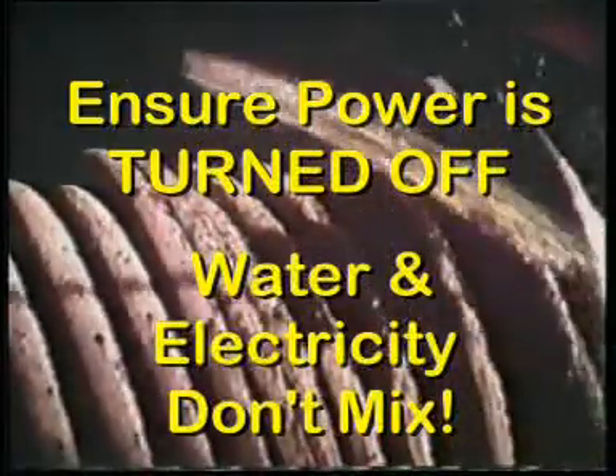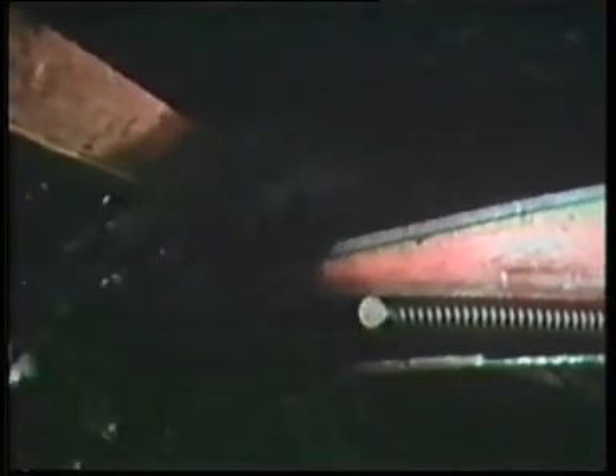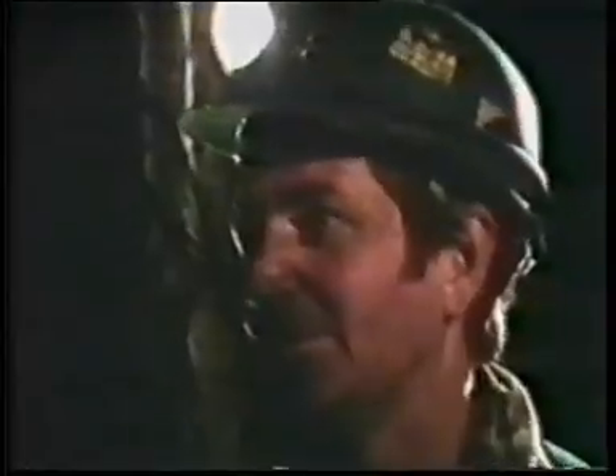Any ignition, particularly in the flame-proof area, could immediately ignite any gas that could be present and puts the entire mine at risk. This hazard can be greatly reduced by ensuring that no more than 2 complete layers of cable remain on the reel when the shuttle car is at the miner. Also by improving ventilation of the reel compartment. Safe cable practice is the joint responsibility of the section electrician and car driver, as well as the deputy. Should a car get bogged, the cable should ideally be removed from the reel before an attempt is made to free the shuttle car.